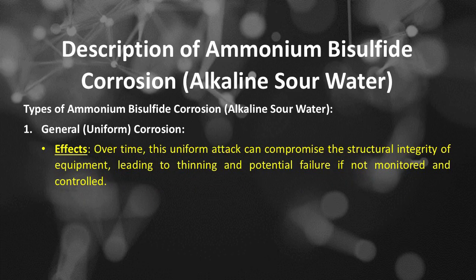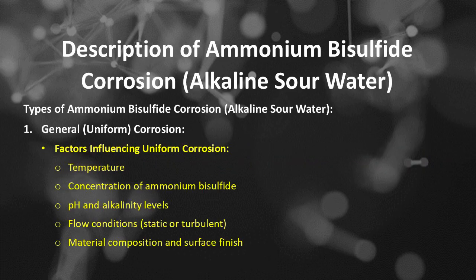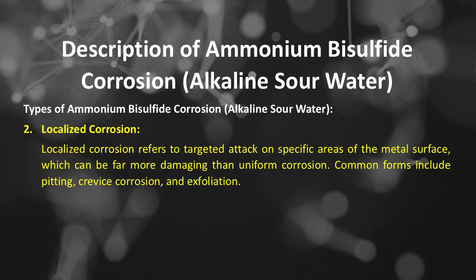The effects of general or uniform corrosion. Over time, this uniform attack can compromise the structural integrity of equipment, leading to thinning and potential failure if not monitored and controlled. Factors influencing uniform corrosion include temperature, concentration of ammonium bisulfide, pH and alkalinity levels, flow conditions, static or turbulent, material composition and surface finish. Number 2 of the types of ammonium bisulfide corrosion or alkaline sour water is localized corrosion.